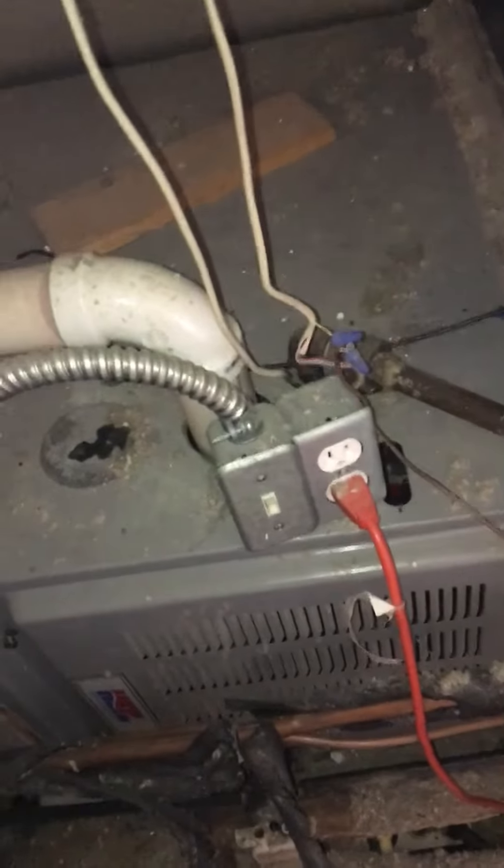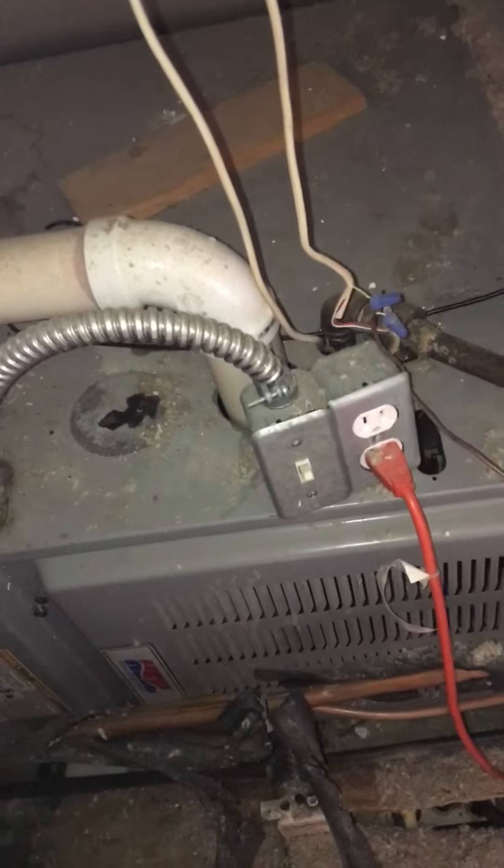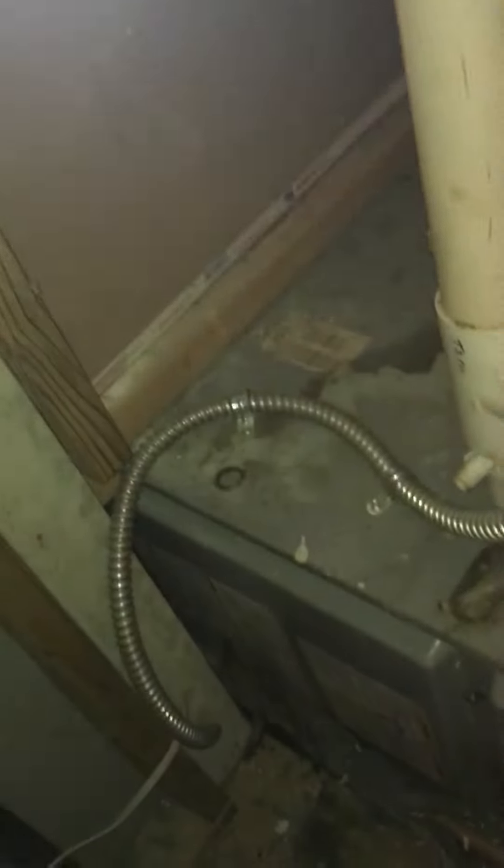We'll need an outlet in this situation — it's a furnace, so we need an outlet, and we'd probably do a light off of that as well. Not too bad of a job overall. Combustion air vent here up high, and we'd need the other one down low. Duct work would have to be excluded until we can dig into this a little bit closer.